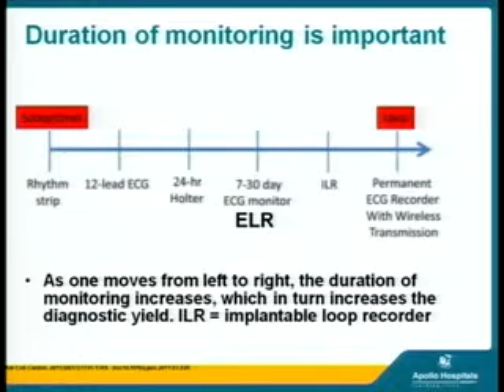These are the various recording systems. This is a standard Holter which we are all aware of. This is an event recorder which is patient activated. The patient activates it whenever the event happens, and when it is activated, immediately it freezes the ECG from just before the activation point. Different event recorders have different durations of freezing the recording, and then it continues the recording for a finite duration after the event. So from the point of pressing of the event, it records the ECG before and after that. And then you have automatic external loop recorders which keep continuously recording and sending the data, and that data gets transmitted to a central server where it can be analyzed.